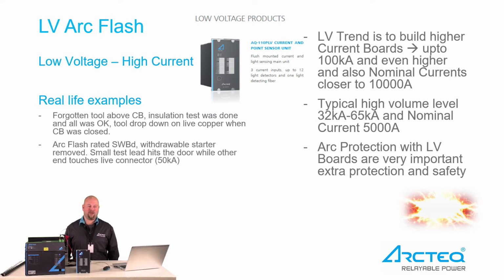The trend is to build higher current boards, quite typically 32 kiloamps to 65 kiloamps boards. Today even lower level kiloamp boards are being built, but the trend seems to be even higher, up to 100 kiloamps, and boards with even more short circuit capability have been built.